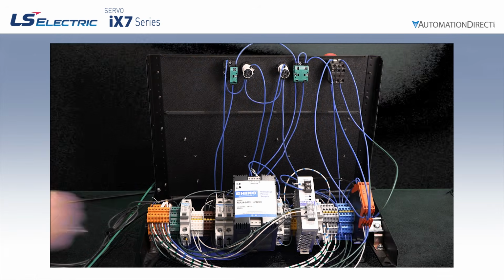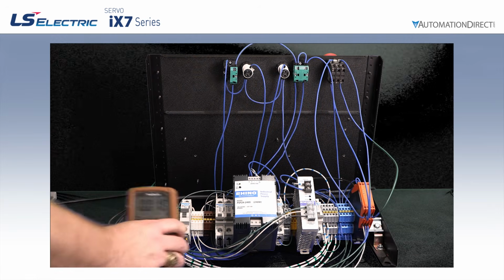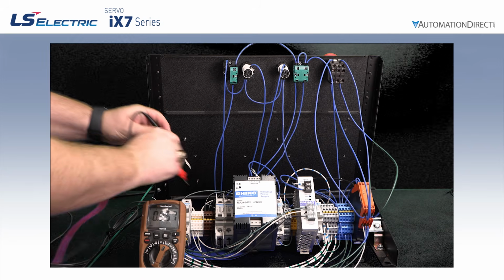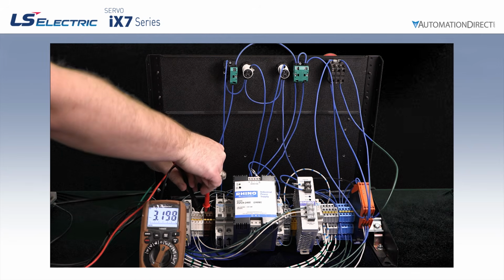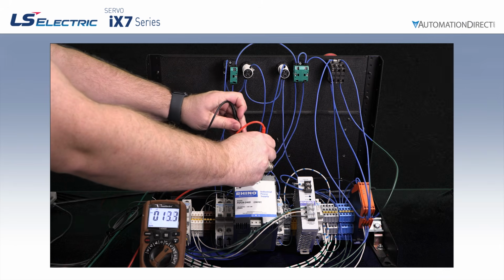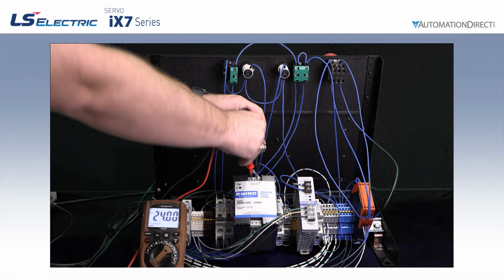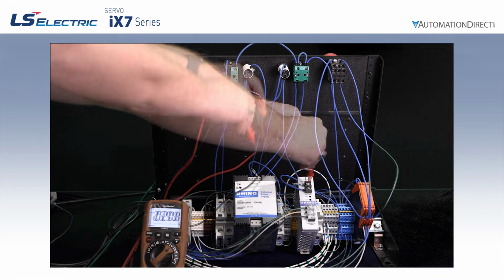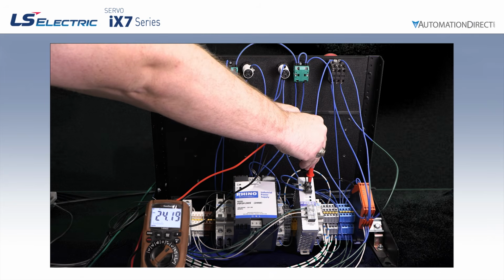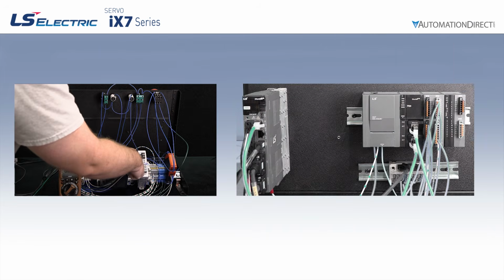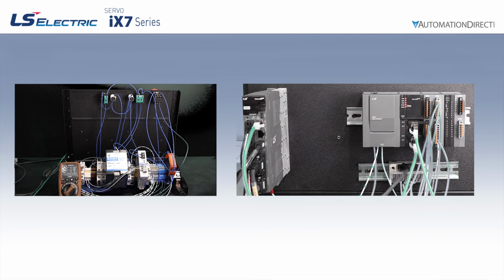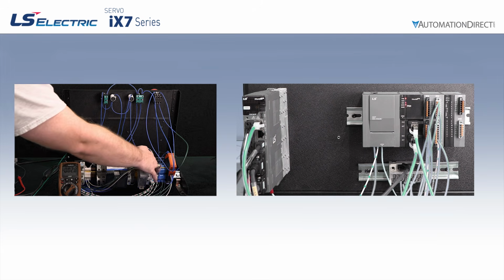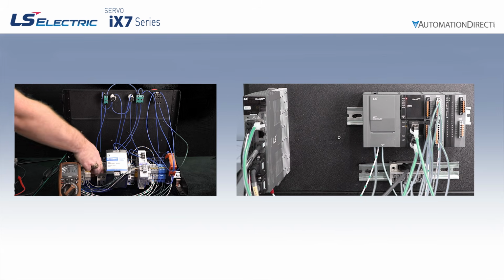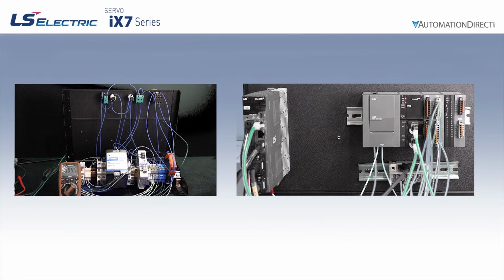Once wiring is complete, we'll turn on the main circuit breaker and check AC input voltage, plus both power supply outputs. Everything looks good. Next, we kick on controller power, and the XMC comes alive. Bringing up the I/O breaker doesn't trip anything, and finally the drive's AC power and controls come up. And the drive powers up without issue. No breaker trips, no mystery smoke. Perfect.